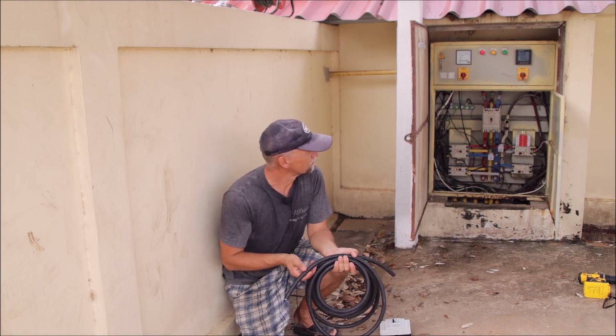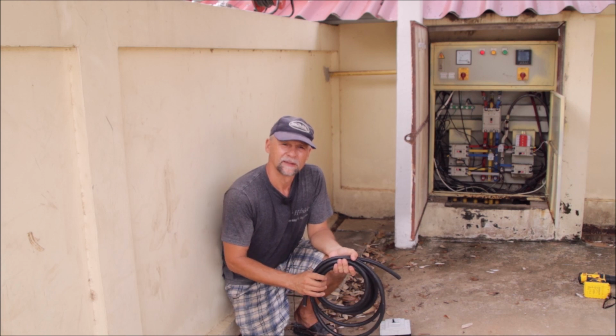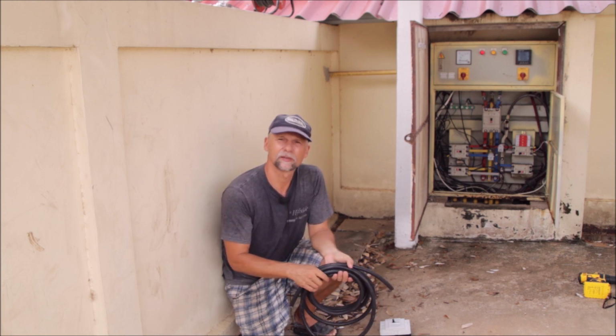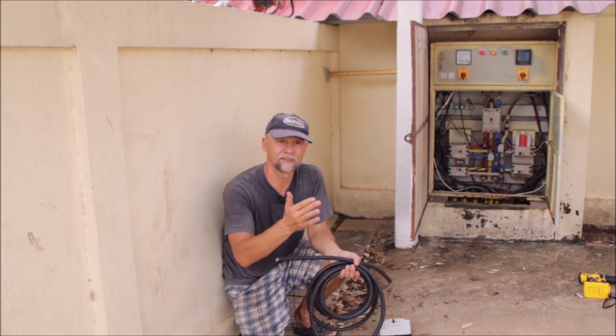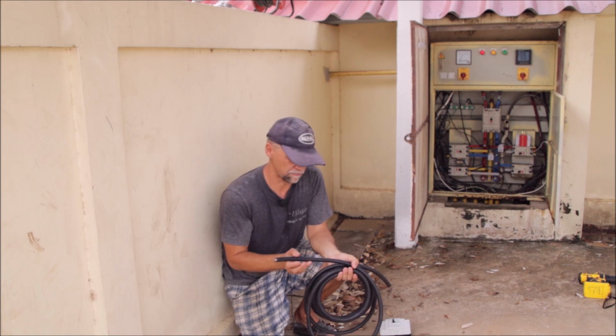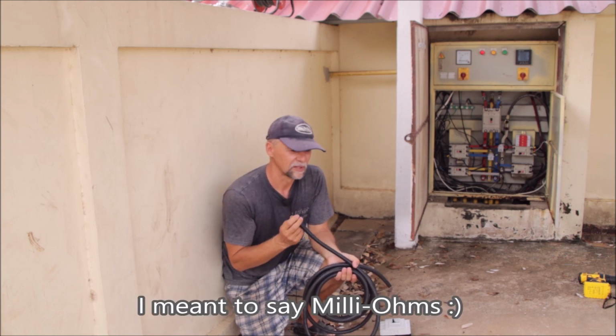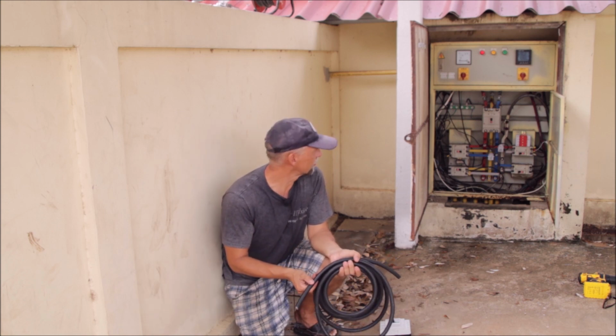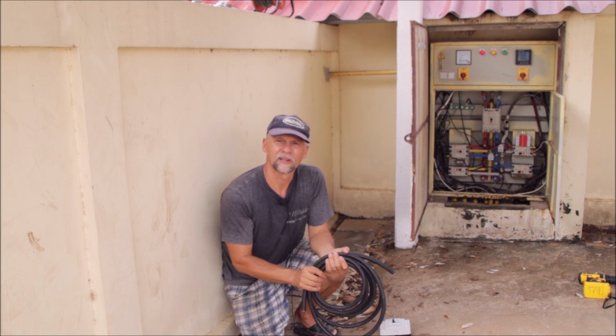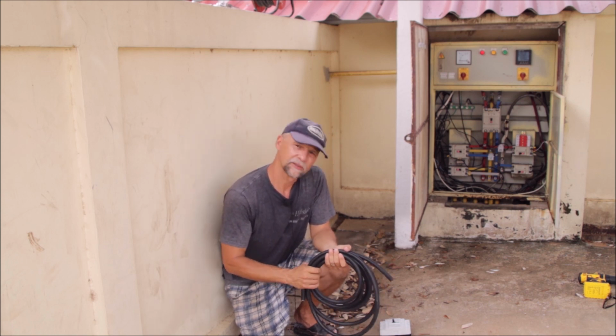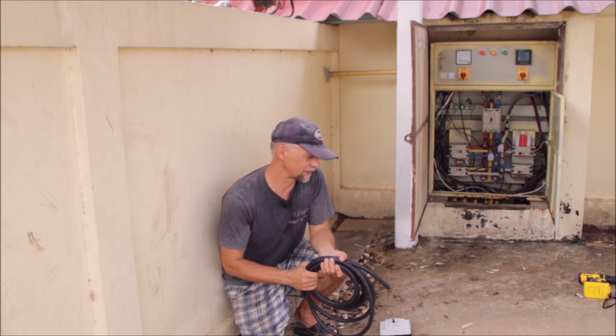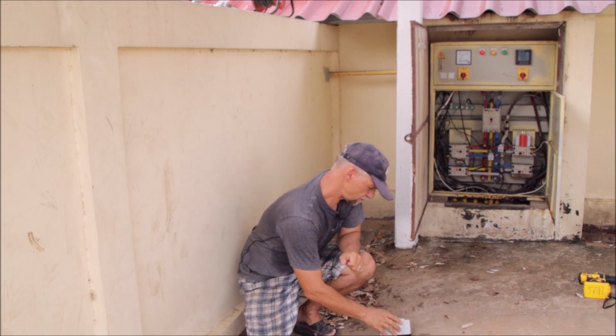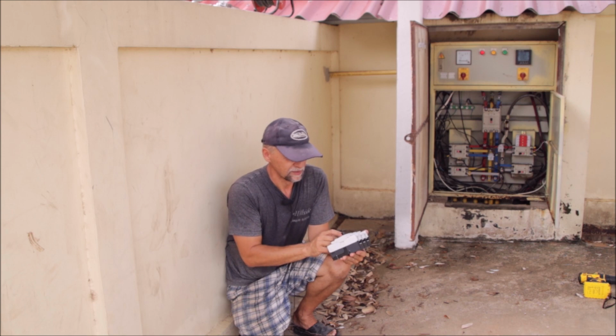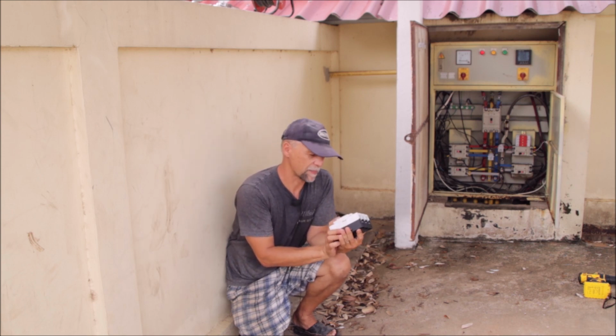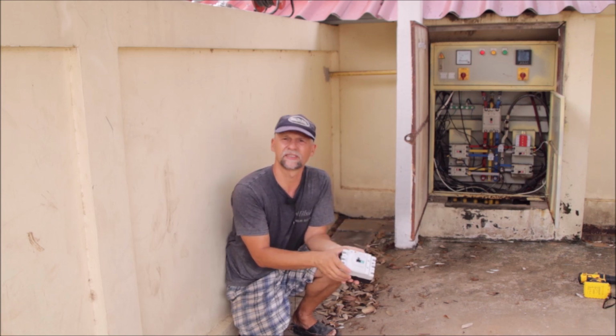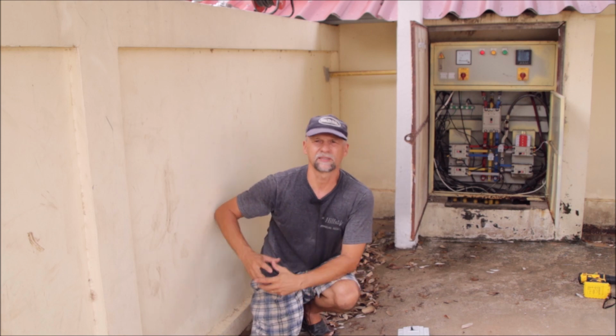So in the case of a short on that line here, we only have a maximum cable distance of around 10 meters, and the 6 square millimeter wire over a distance of 10 meters there and back only has a resistance of around 30 milliohms. So if there's a short 5 meters away from the MDB, there would be a current of around 7,000 amps flowing, right? If the transformer can put out that current for a short time, this could really happen. That's why these breakers have surge current ratings in case of short circuit, up to, like this one here, 7,500 amps. So these are massive currents.